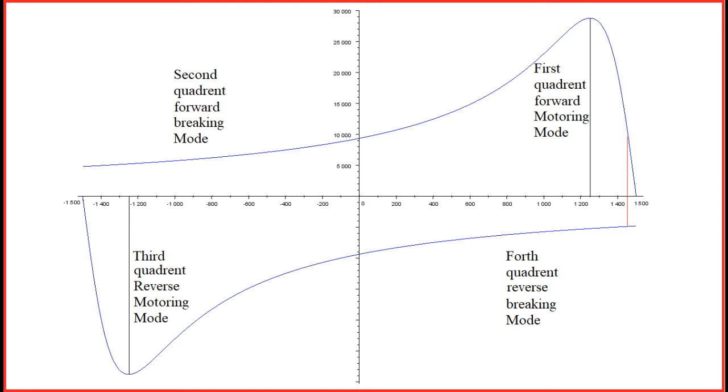The characteristic curve of three-phase induction motor that we saw in previous lecture was slip versus torque or mechanical output. But now we are looking at torque speed characteristics. In the first quadrant, induction motor runs in normal mode with both speed and torque positive. When electric supply is connected to motor, at the beginning speed is 0 and corresponding y-axis or torque axis showing starting torque. Initial hyperbolic portion of characteristics showing increasing torque with increasing speed is an unstable part of characteristic curve.